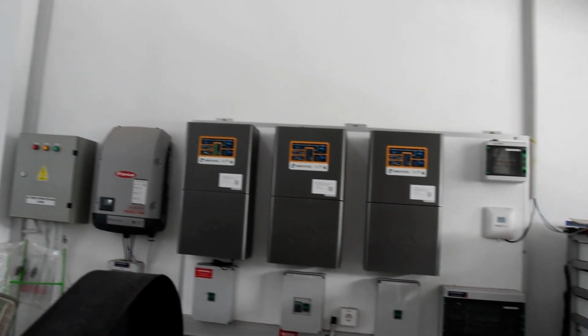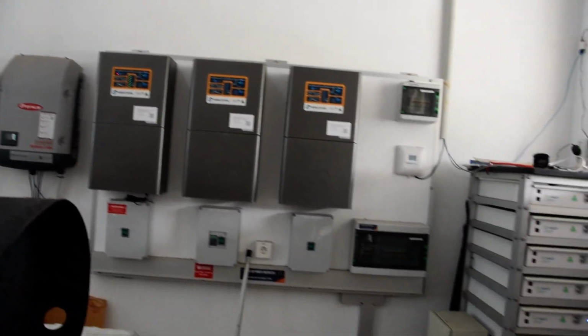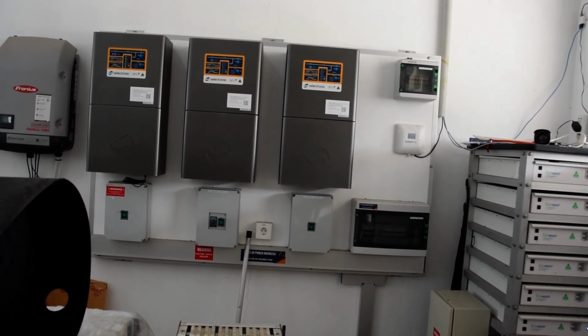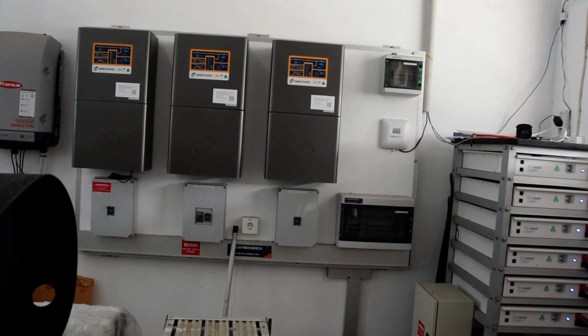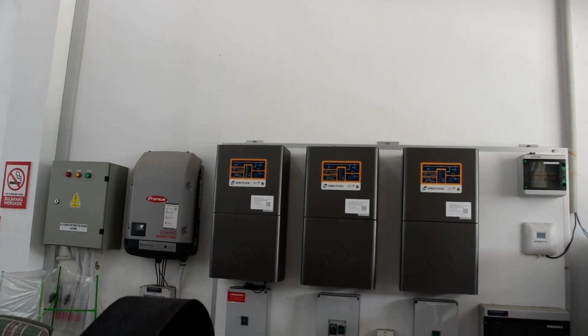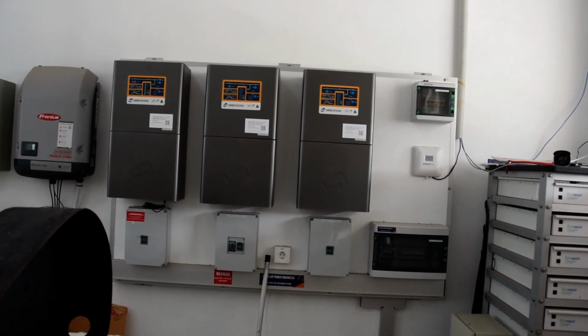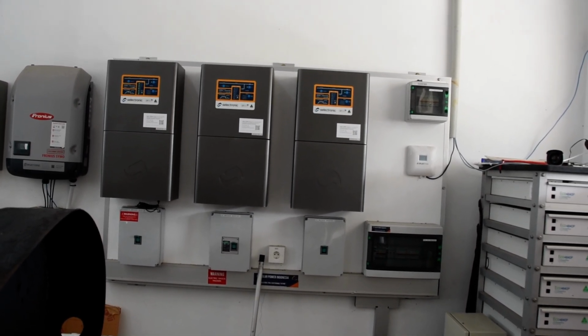I wonder why it's blinking red up there. Oh, I think it's to do with the genset. Now, after a thunderstorm a couple of weeks ago, the diesel genset has got a problem with its auto start function. When it's set to auto start, it wants to start and run independent of control by this thing, which is not correct. So I'm still waiting on technicians to turn up and look into that. Hopefully they'll come here by the end of the month, but oh well, yes they don't.